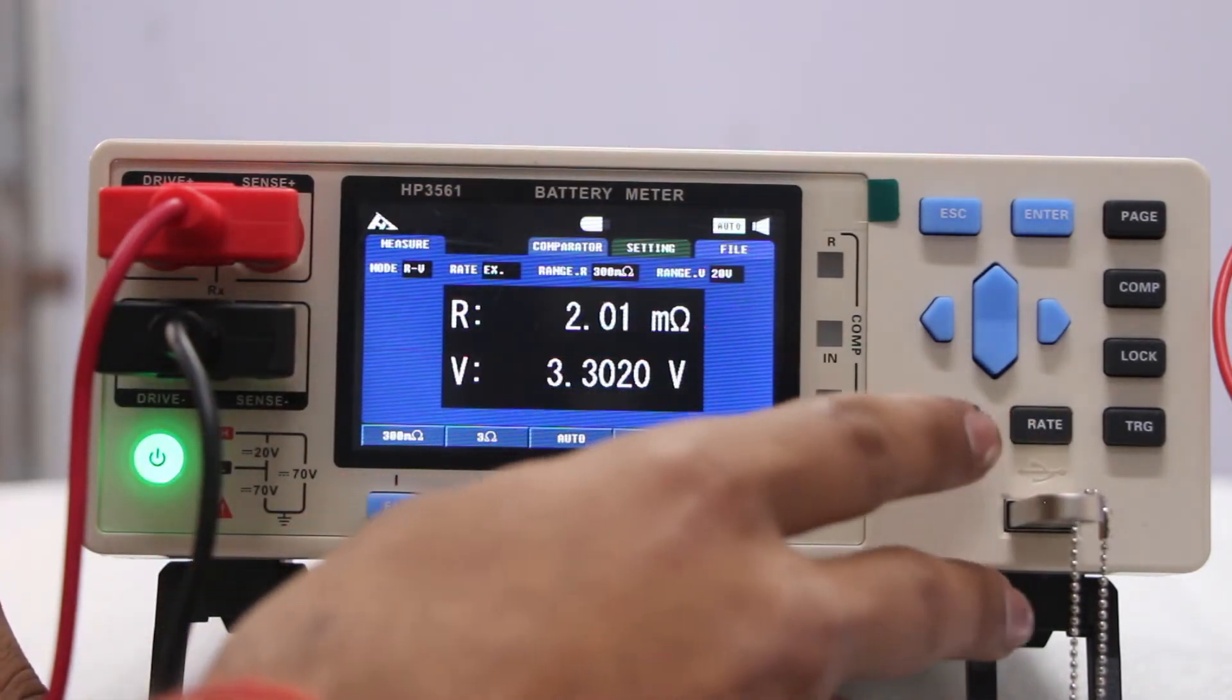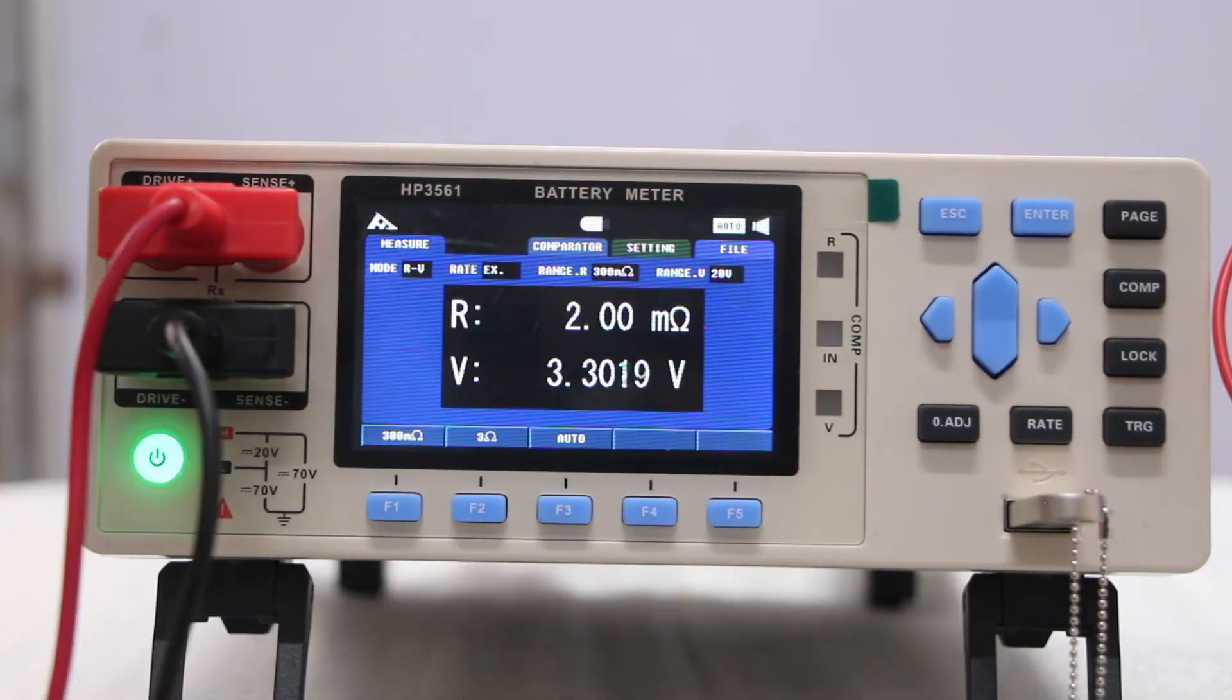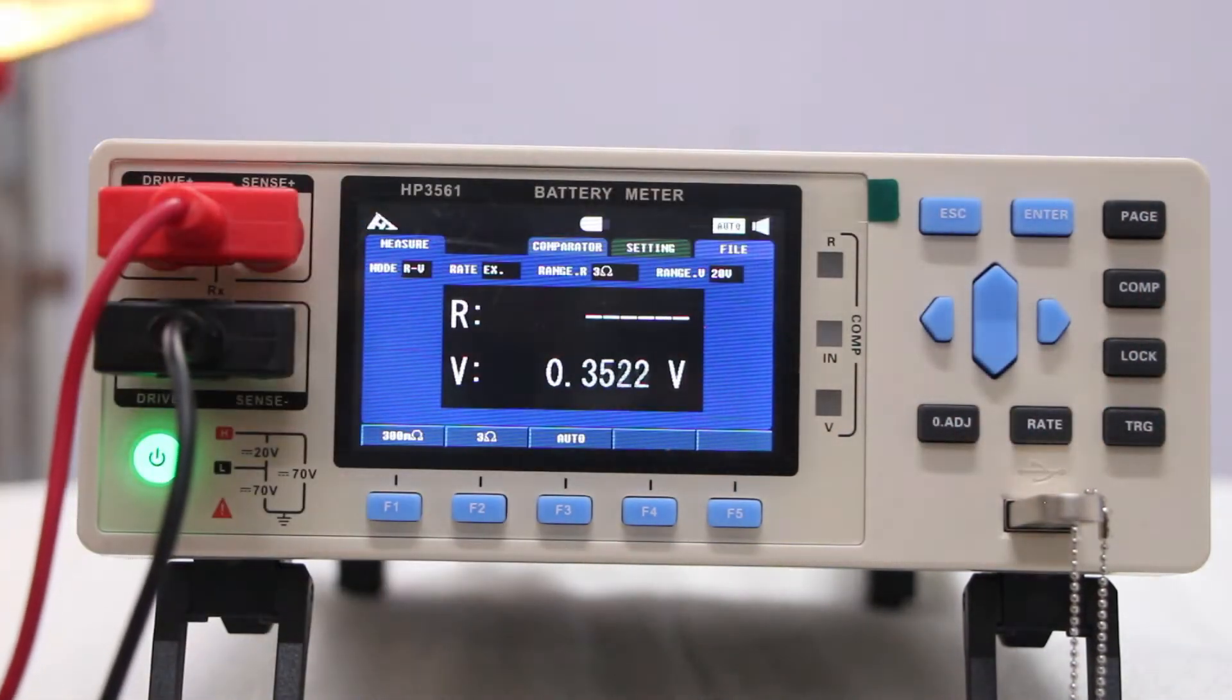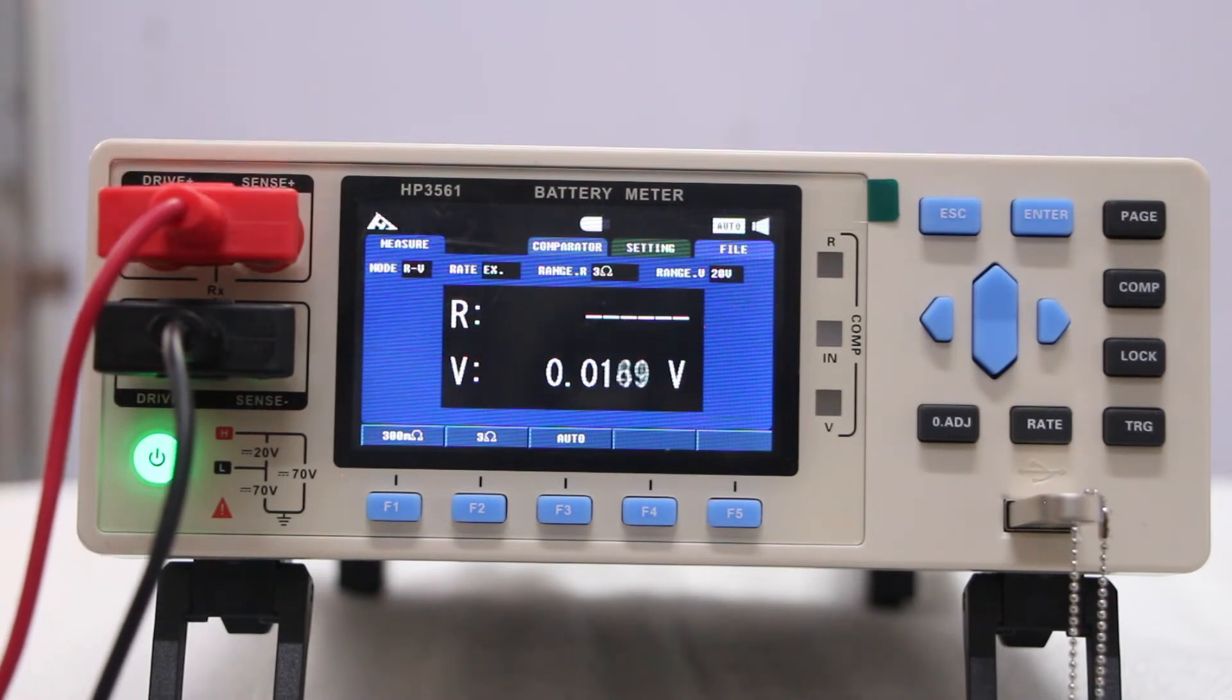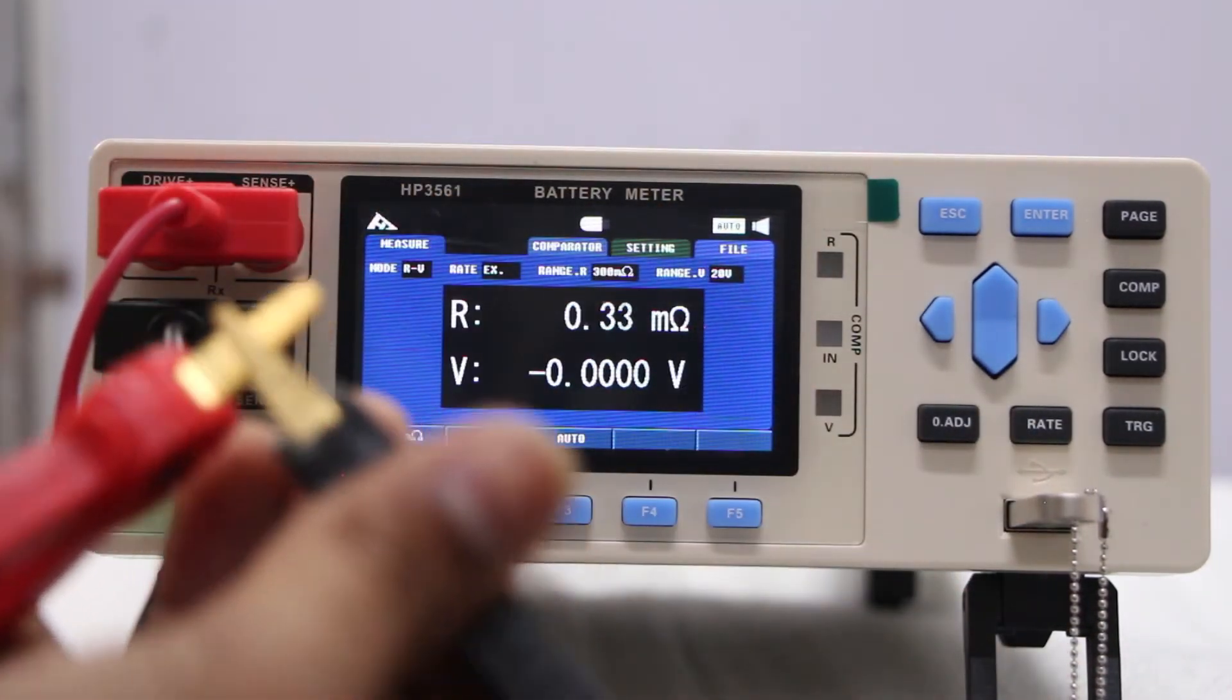As you can see that there is a zero adjustment. Zero adjustment purpose is like sometimes when you are not getting a proper IR means it might be possible that the machine may be not precise or not adjusted at zero. At that time you have to use zero adjustment.